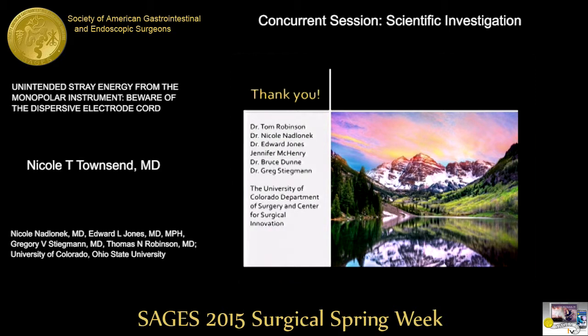Did you look at any non-monopolar devices, like, for example, bipolar or ultrasonic, to see what that was like? Absolutely, and because the bipolar device in the electrical circuit is within the device itself, it doesn't participate in antenna coupling anywhere near the amount of the monopolar instrument.